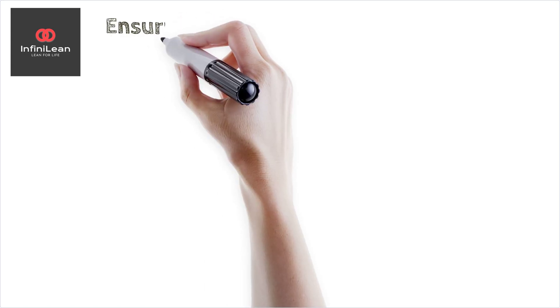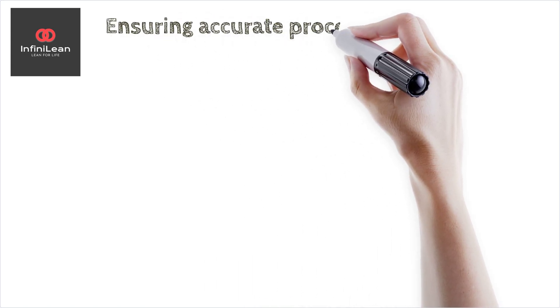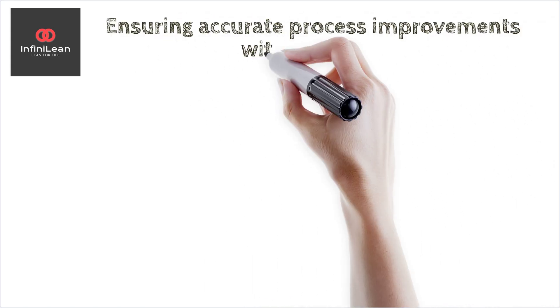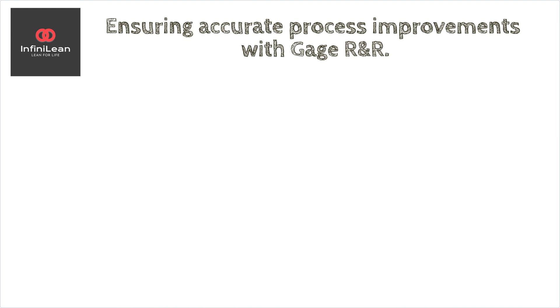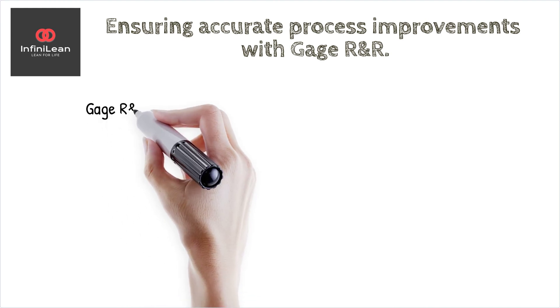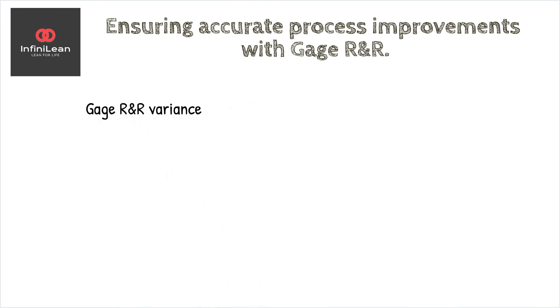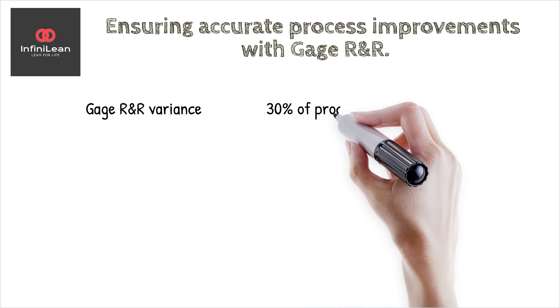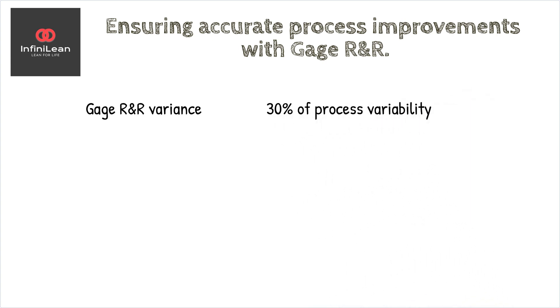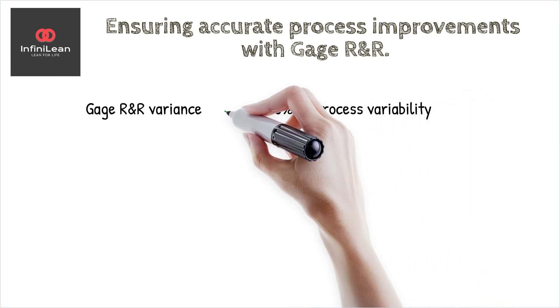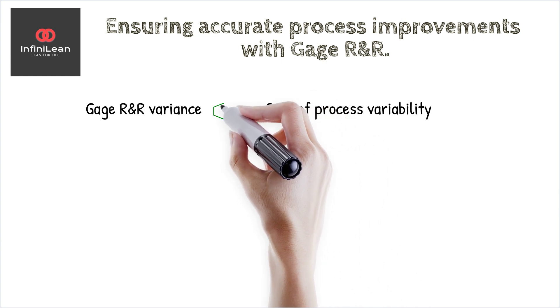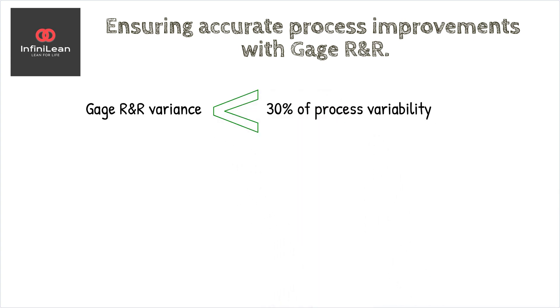A common rule is that the Gauge R&R variance should be less than 30% of the process variability. Anything higher might require improvements in the measurement system, such as better operator training, equipment calibration, or more precise measurement tools.